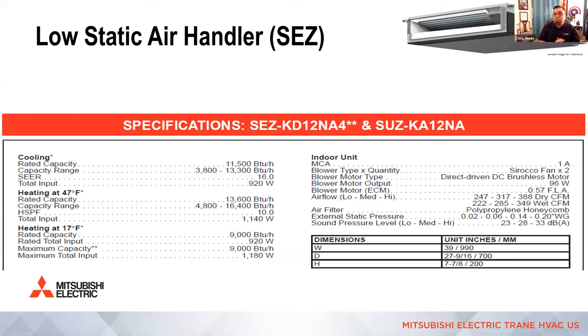Also, it's really important to note that all of the low static air handlers for Mitsubishi ship at a medium speed of a static pressure of 0.14, all right, which is very low. It's probably not enough static pressure to even handle any air filter you attach to the system. So when we design with an SEZ, our low static air handlers, we actually design around max static. It's the only way we're going to be able to connect ductwork to the system.